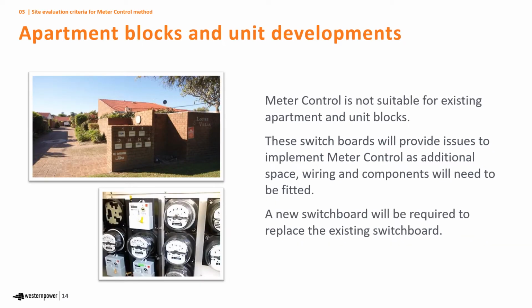The next area that will be problematic and should be able to easily be assessed from a site evaluation is apartment blocks and unit developments. These sites often have meters that are grouped, and that causes difficulties, particularly around needing additional space. If they're older style meters, then the new meters may not fit in. In some of these apartment blocks, you'll have what's called a plug-in meter. These plug-in meters are not suitable for meter control, as they're not set up for that.